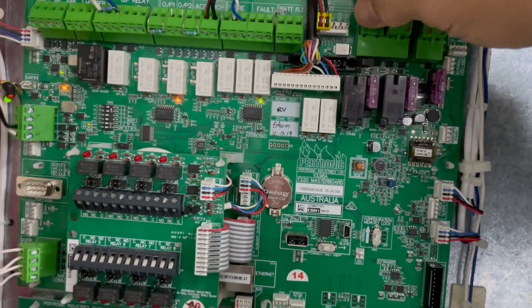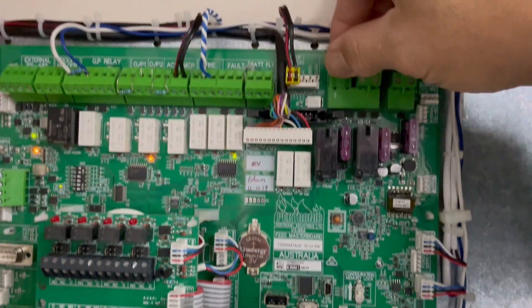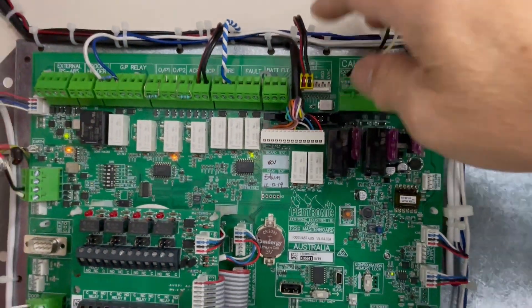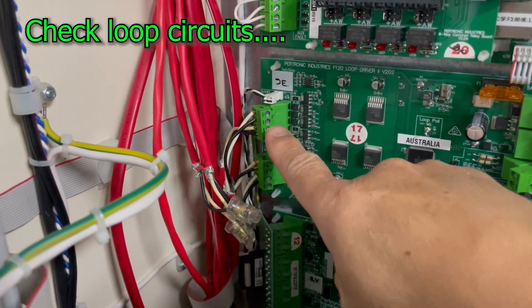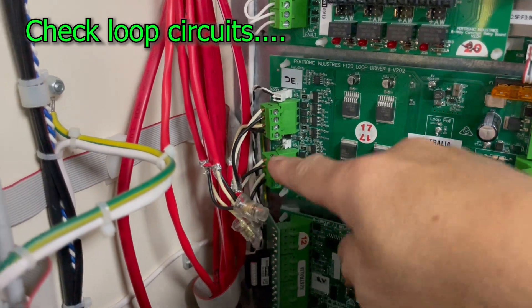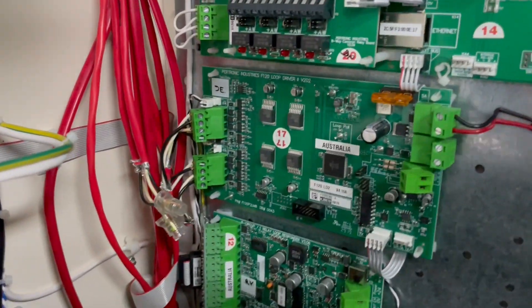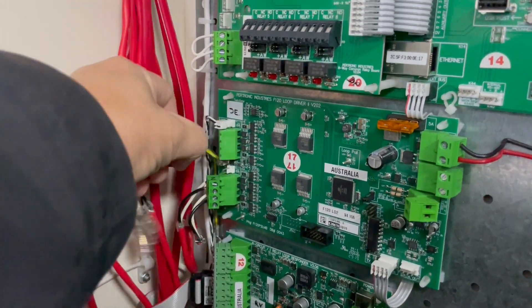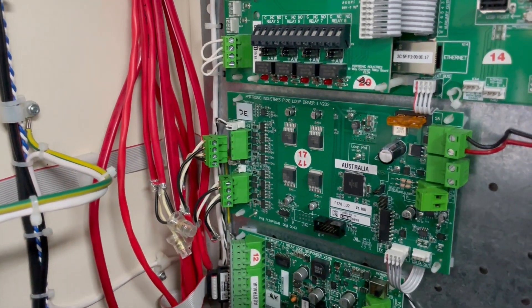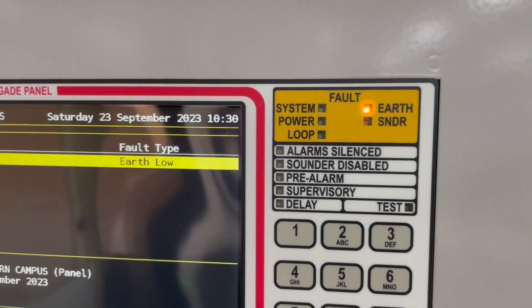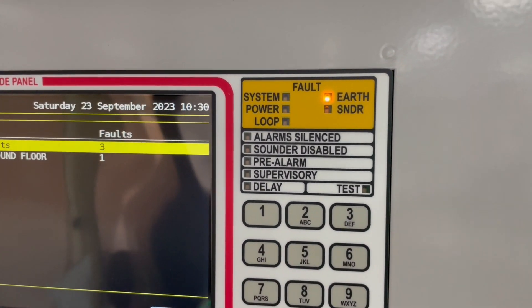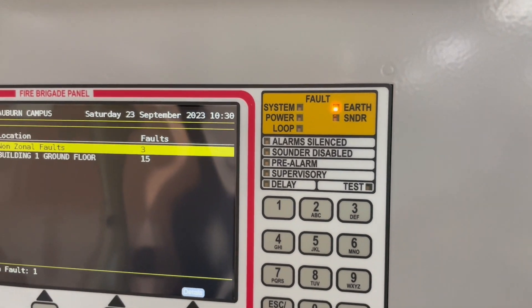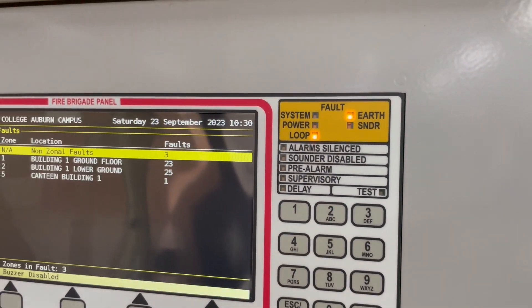And then plug it in. What are the other possibilities? Let's look on the loop card. We got loop one and loop two. Let's plug out loop one and check if the earth fault still exists. Earth fault still there. So that's not the source or the origin of the earth fault.